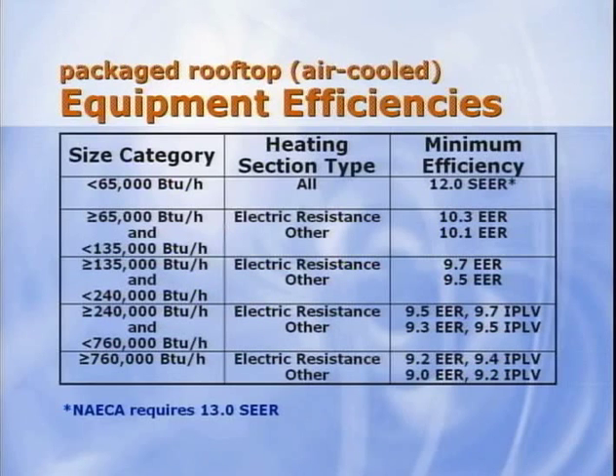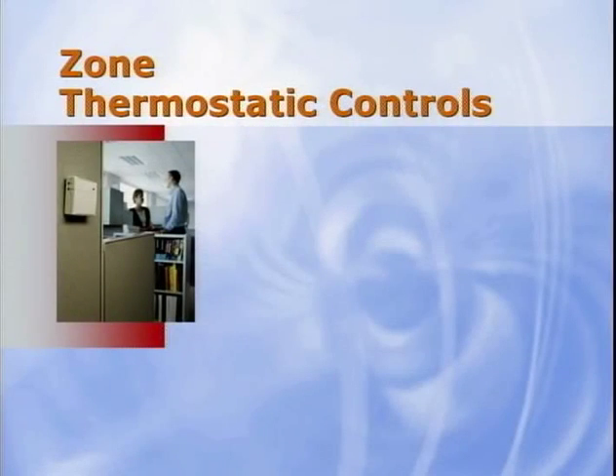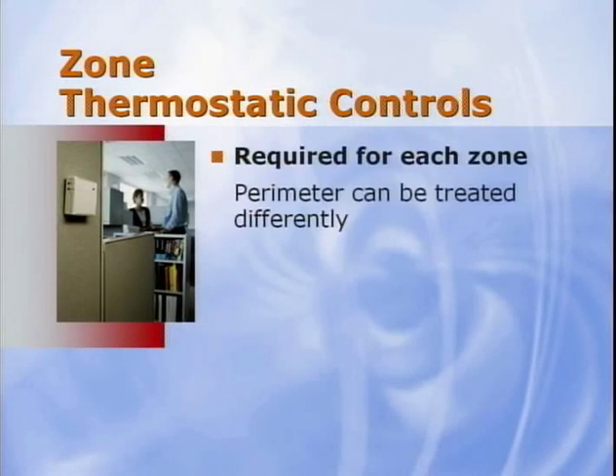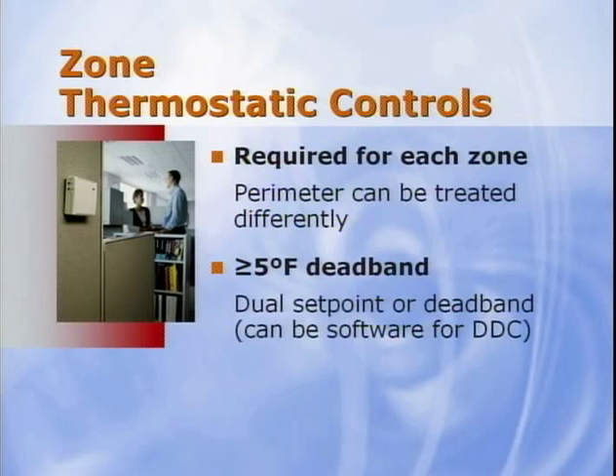Please note that when both a full load energy efficiency ratio, EER, and integrated part load value, IPLV, are listed, both must be met at the standard rating conditions. There is also a mandatory section on controls. Thermostatic controls are required for each zone, not room, but thermal zone. In addition, there is a requirement for the capability of having a 5 °F deadband, which is the difference between when cooling is enabled and when heating starts.